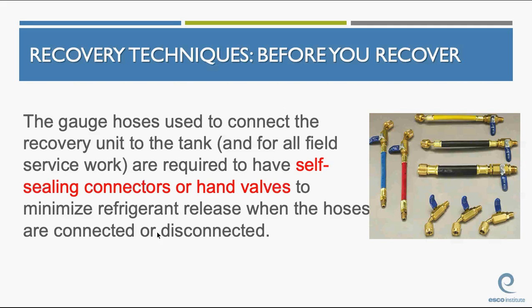A gauge hose is used to connect the recovery unit to the tank. For all field service work, you have to have self-sealing connections or hand valves to minimize refrigerant release when the hoses are connected and disconnected. You've got to use valves, got to use low-loss fittings.